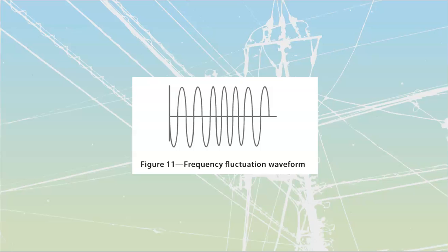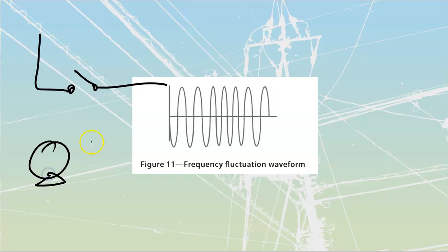We get a lot of cogen sites involved in lumber processing, where we take all the bark, branches, and offcuts and burn that inside huge furnaces. We use those furnaces to heat steam and run that steam through steam turbines. BC Hydro comes into our facility, and our cogen generator synchronizes with that BC Hydro supply to help carry some of that power. Anytime the cogen can't carry enough power, we take the rest off BC Hydro, and anytime BC Hydro isn't needed, we should be supplying everything through the cogen path.